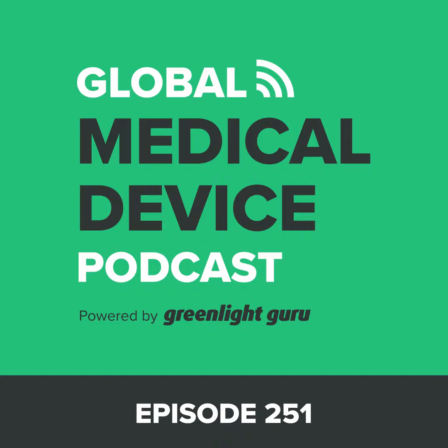Now, part of the regulation talks about the device master record, all the information required to build the product. Well, the DMR is actually a design output. So the DMR is actually part of your design history file. You can debate this with auditors, but it doesn't matter. As long as you have them, you need to have them, and they need to be controlled. So your design output, device master record, is everything you needed to build the product. So what do you need to build the product? Well, all the parts in the product need to be listed and defined and controlled.